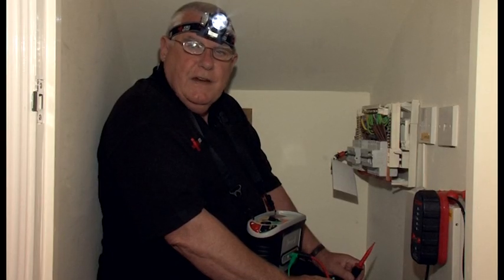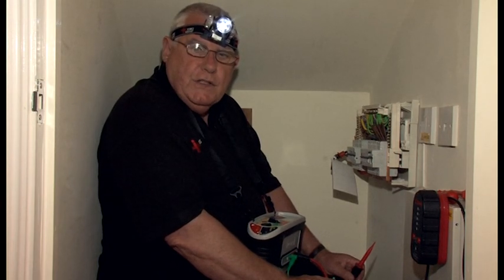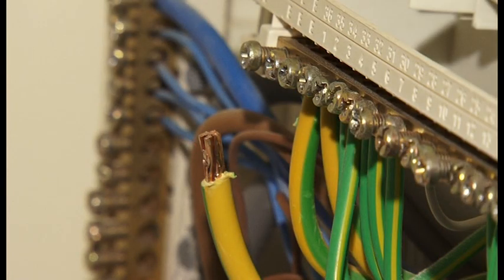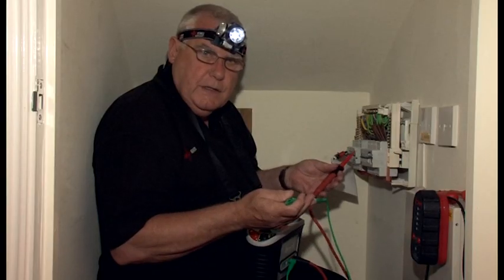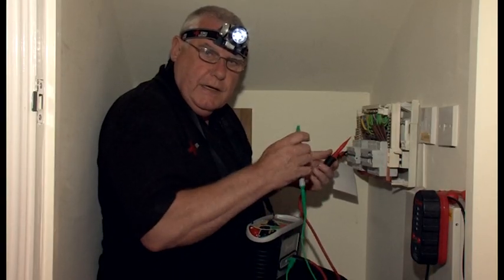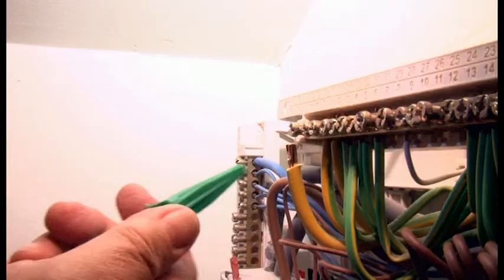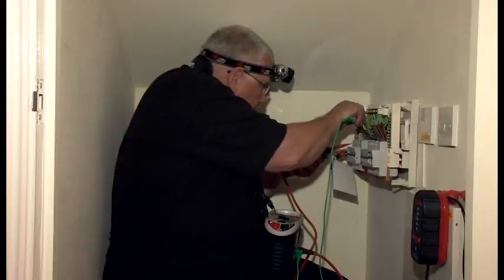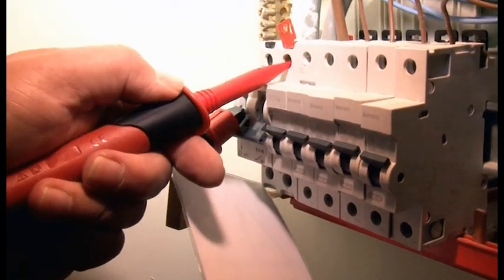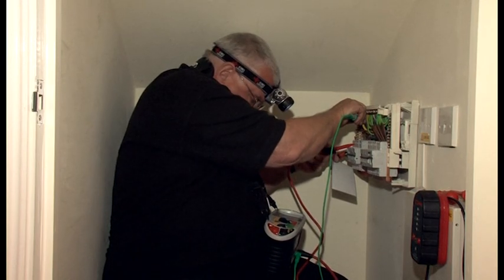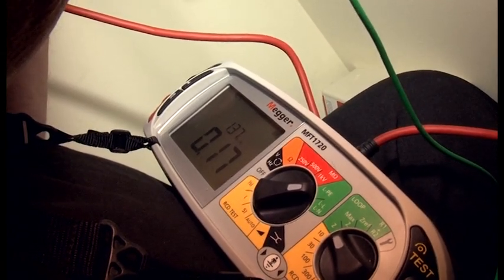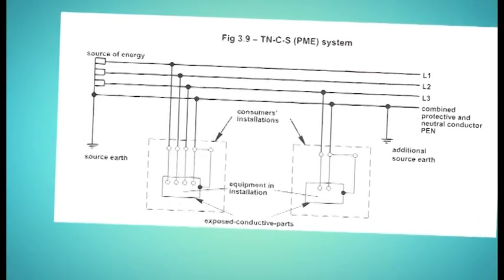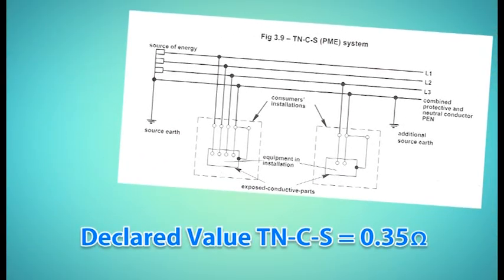What I'm actually going to do is to verify the prospective fault current for the installation, which is the highest impedance reading of two tests. For the first, which is prospective earth fault current, as you can see, I've disconnected the earthing terminal from the MET. Now this instrument only needs 2 leads for this test, so I'm connecting first to the disconnected earth conductor and then to the incoming line. And the reading I've got is 0.17 ohms with a PFC of 1.37 kA. The distribution network operators declare the value of impedance for a TN-C-S supply to be 0.35 of an ohm.